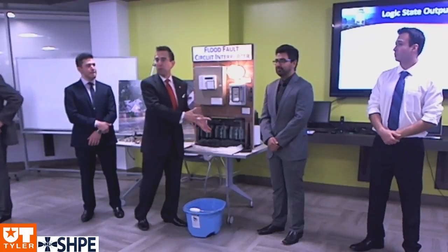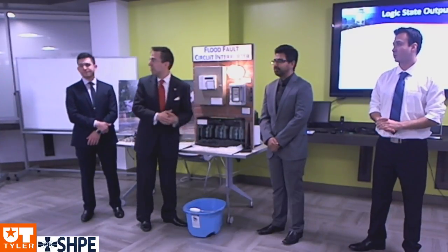So if you came up closer, you might be able to see how it would be enclosed and have a filter in there. Okay, gotcha. Correct, and it's minimal because, in part, the other good news about these float switches is that as long as any liquid gets in there, they're very reactive. There's not a lot of resistive force to floating those switches.